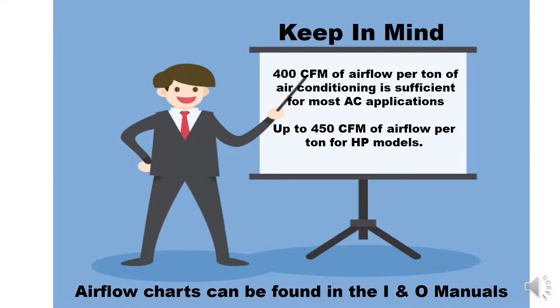Keep in mind, 400 CFM of airflow per ton of air conditioning is sufficient for most AC applications. Up to 450 CFM of airflow per ton for heat pumps may be needed. Airflow charts can be found in the I and O manuals.